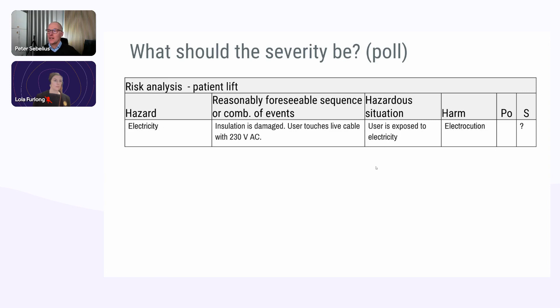In this case, the insulation has been removed, and the user touches the live cables inside and is exposed to 230 volts of alternating current. And that's obviously not a good thing. So I've written this up in a risk analysis, and I'm saying that the hazardous situation is that the user is exposed to electricity and the harm is electrocution. Now, I want you to get involved a little bit because I want to ask you, what do you think the severity of this risk should be? I've added the definitions here, ranging from 1 to 5, inconvenience or temporary discomfort, all the way to death. So I would love to hear from you.